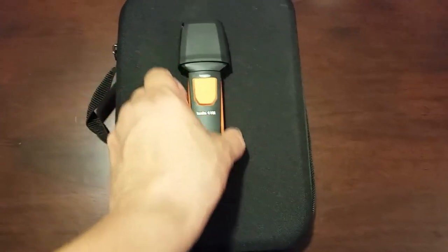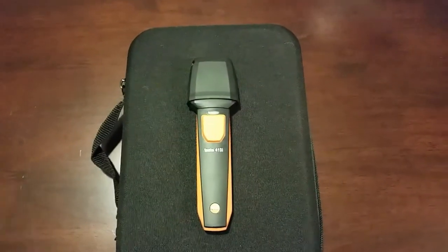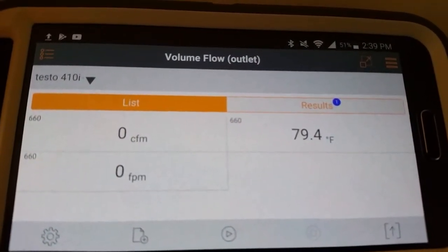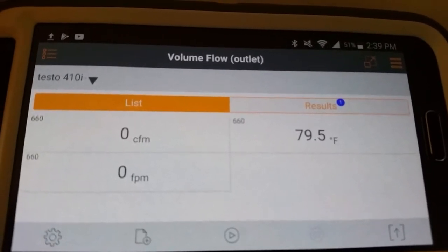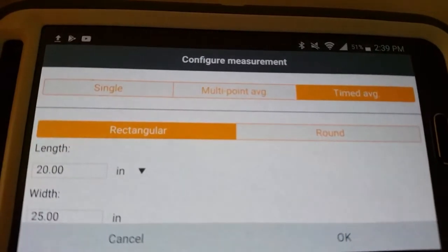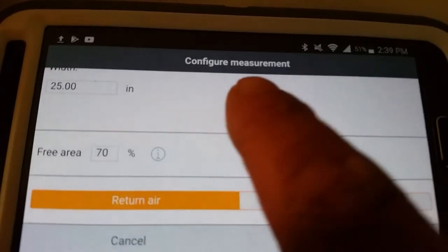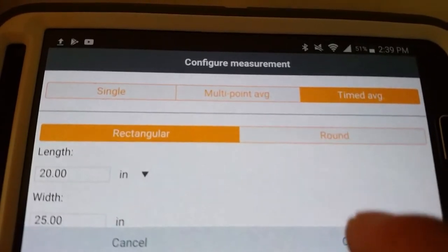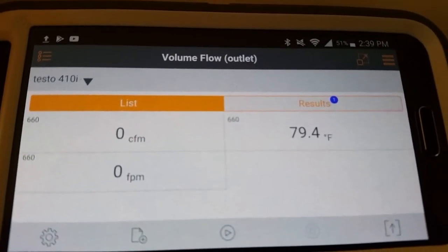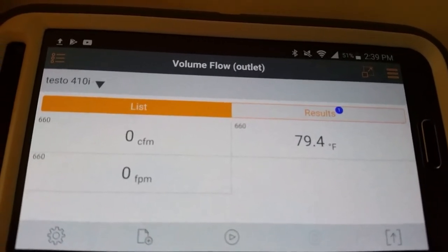Really like these Testo smart probes. We are going to connect this to our phone and go over to the grill to get the traverse started. We've got the Testo 410i connected to our smart probe app. If we go down to the gear icon for settings and then configure measurements, you can see we have 20 by 25, scrolling up we're at 70% free space and return. At the top you can see we are set to timed average, which is the best method when doing airflow testing because you're going to get different velocities and different CFM in different areas of the grill.